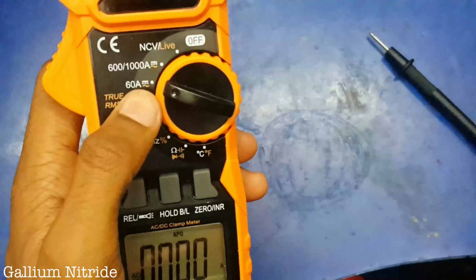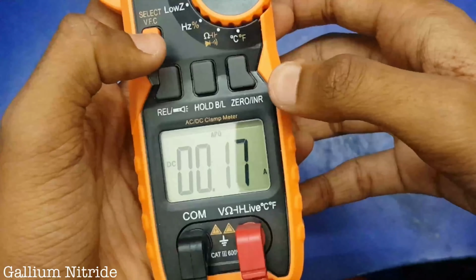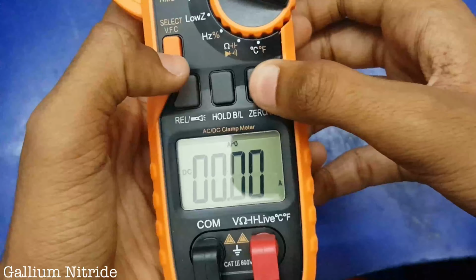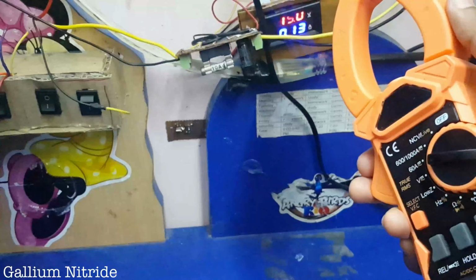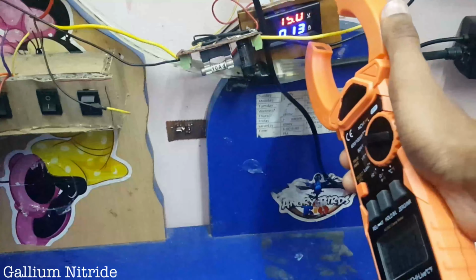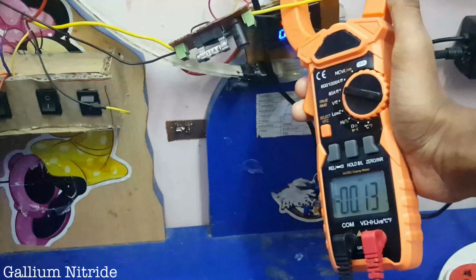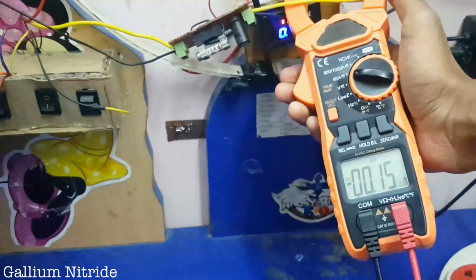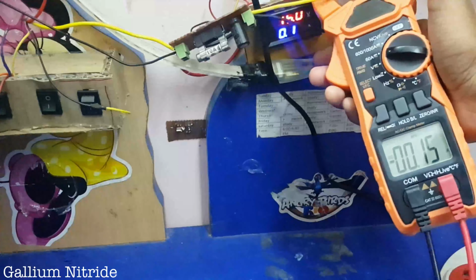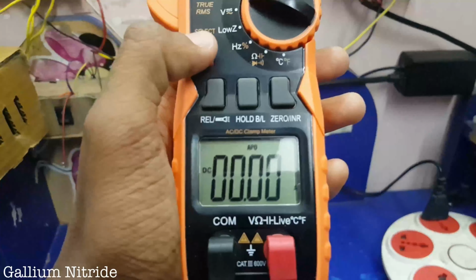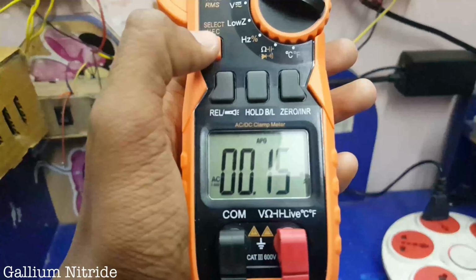Next up is main current measurement. For DC, let's check out my 12 volt power grid first. I set it to DC and hit the 0 button to remove the excess current caused by the earth's magnetic field. It measures the 13 milliamp current flowing as 15 milliamps, which is still within the accuracy range of this meter.